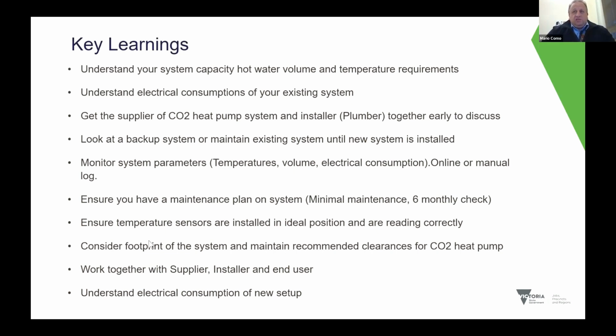Ensure temperature sensors are installed in the ideal position and reading correctly. Temperature sensors installed on the top section of the tank compared to the bottom section can give you different temperature readings. Consider the footprint of the system. Maintain recommended clearances for the CO2 heat pump: front, rear, sides, and even the top, you should have clearance as per the design of the unit. Work together with supplier, installer, and user to achieve the result, which is what we had to do. Understand your electrical consumption of the new setup as the final step.